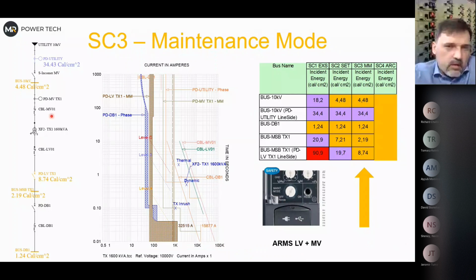For us, it works this way: we drop the settings to the barely minimum, so it should still operate. But for us, safety was more important at this moment. And that's it. But we lose selectivity this way, because you see this is not selective anymore with the downstream breakers. So there's something for something. I did the same, you don't see it here, the programmed arc flash reduction switch for the medium voltage relay as well.